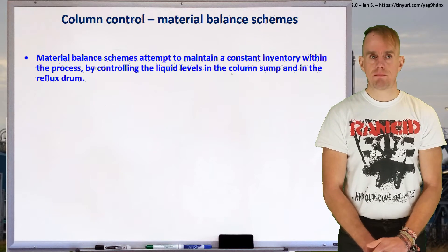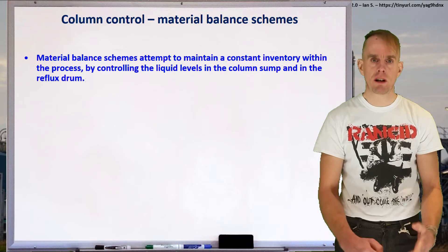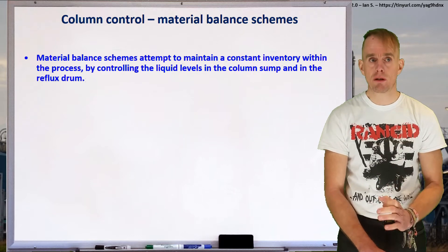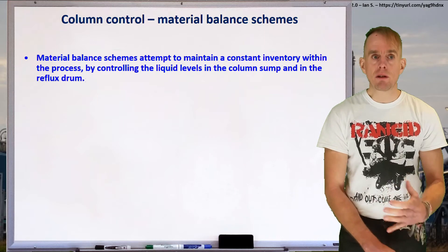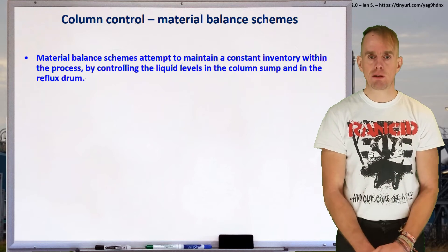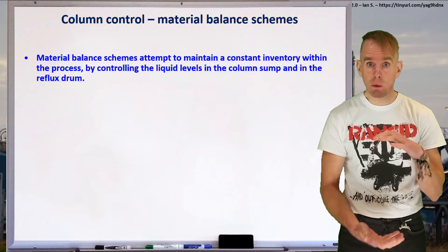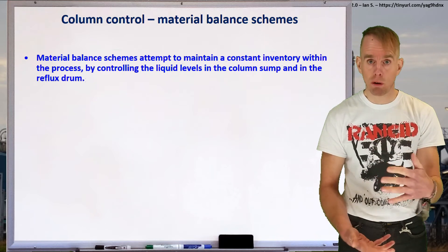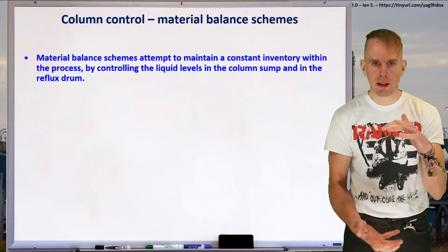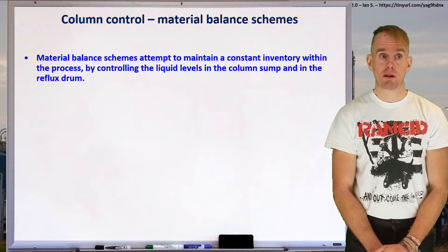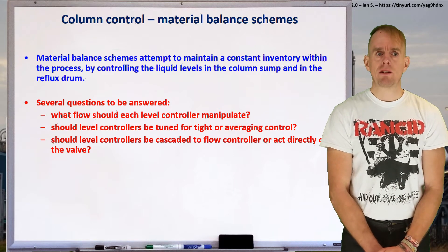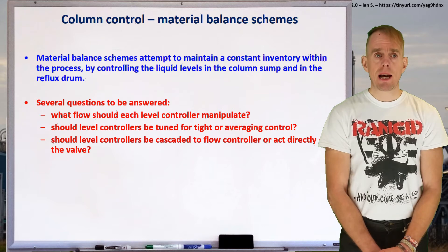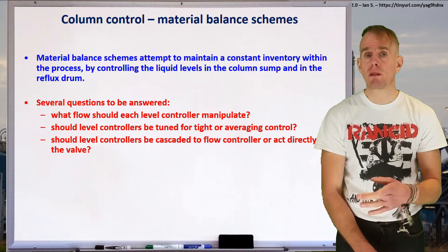Let's turn our attention now to the second question: how do we control our column for the given scenario it's operating in? Let's talk about the first of these two schemes — material balance schemes. Material balance schemes attempt to maintain a constant inventory within the process, and they do this by controlling the liquid levels in the column sump and in the reflux drum. In the base of a distillation column, you have liquid holdup called a sump, typically with five to seven minutes' worth of holdup under normal flow conditions. If we elect to use a material balance scheme, we need to figure out which flow each level controller should manipulate, how that flow controller operates, and whether level controllers should be cascaded onto flow controllers or act directly onto the valves themselves.